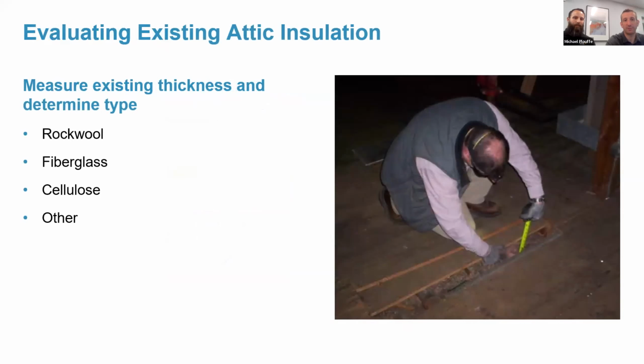In terms of inspecting attic insulation, one thing first and foremost to note in this photo is that this gentleman is using PPE. You want to make sure that if you're going into an attic space, you're taking steps to protect yourself from potentially hazardous materials, particulate matter, things along those lines. Here, this gentleman's wearing gloves. It appears that he's wearing protective eyewear and a mask. So those are definitely things you want to wear anytime you go into an attic space. And what he's doing here is measuring the insulation thickness through a removed section of floorboard in the attic. So we want to identify the material type and thickness to see if there may be some cost-effective opportunity there to improve upon the existing conditions.